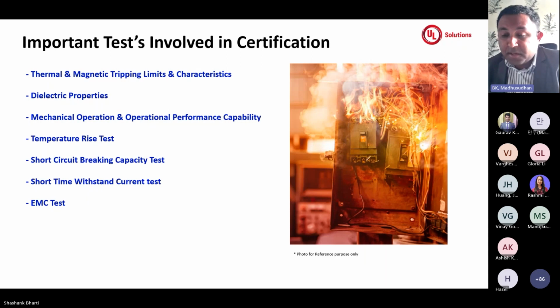And again, if the breakers are declared as enclosure type, they will be put in the enclosure and the test will be conducted. And if it is declared as unenclosed type, there is a standard requirement that we have to put a mesh covering the complete surface of the breaker. The declaration for the dimension of these meshes has to come from manufacturers. The breaker will be mounted, and above that the mesh will be connected, and all the ground fuses will be connected during the test. And during the observation, all the fuses connected to the ground should be intact.